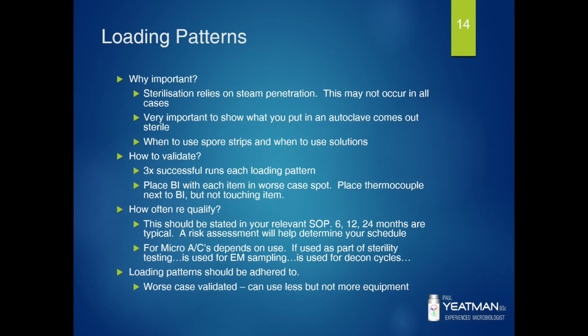With terminal sterilisations, steam penetration won't occur if the containers are integral, which they should be. So you will need to place vials containing spore strips amongst the loading pattern to show nothing grows in the vials, and cycle validation is critical to show unadulterated product. So even 1 CFU in a vial could be disastrous if injected into a patient.